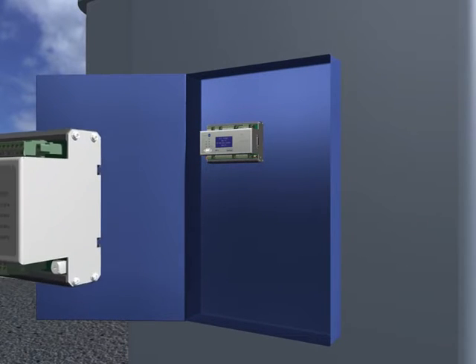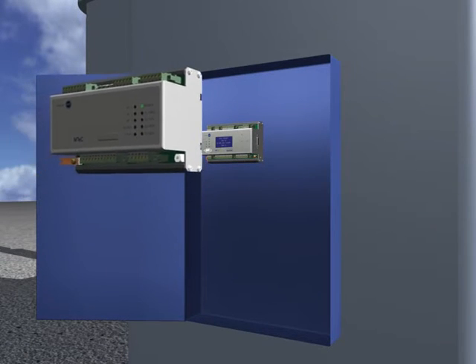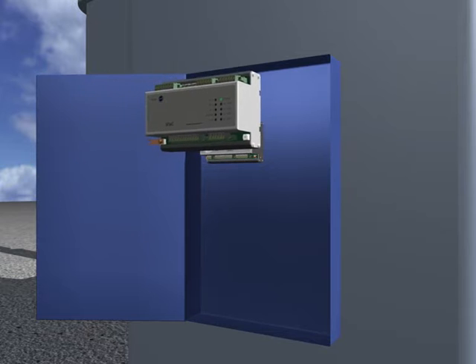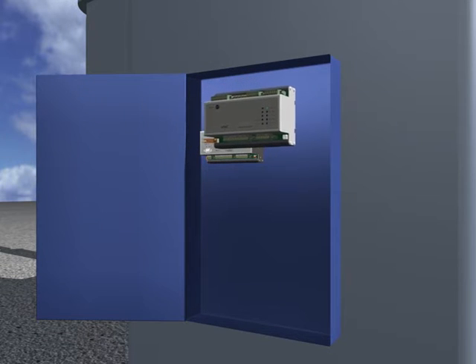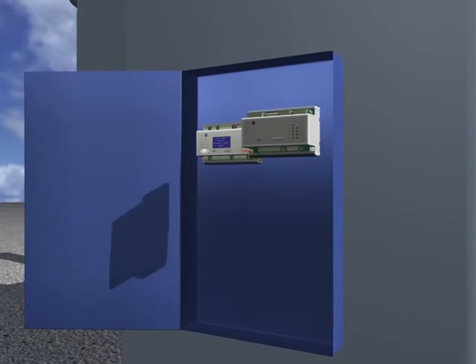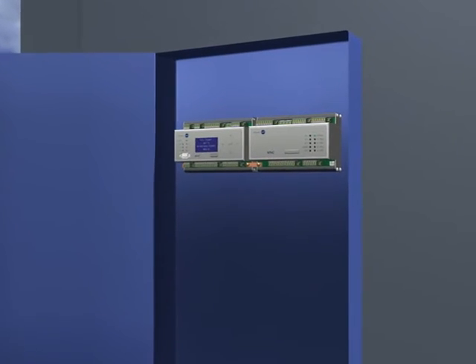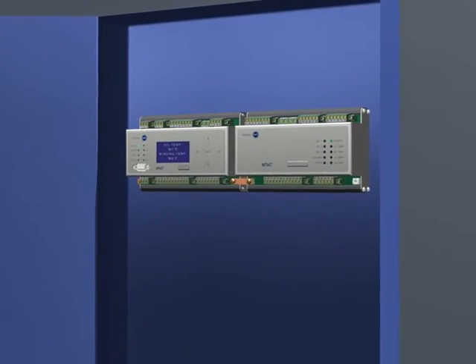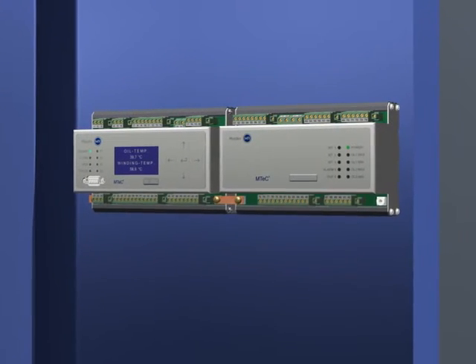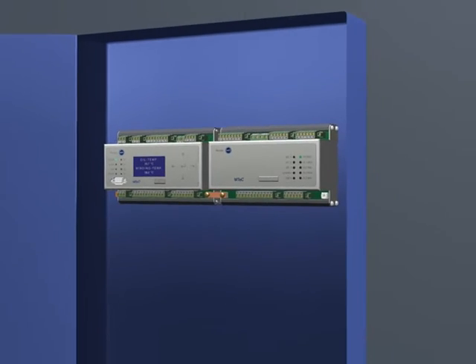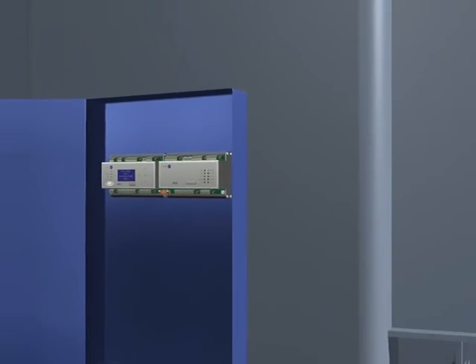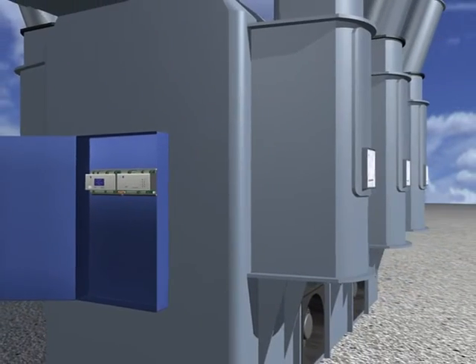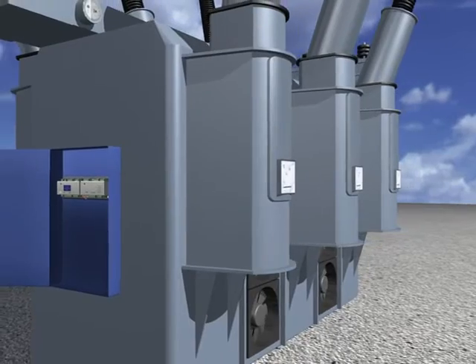Click on an extra module to expand the functionality of the MTeC system with additional circuits to monitor winding temperature and oil level. We are talking about function modularity here. It is important to measure the winding temperatures of all transformers which are equipped with cooling systems to increase loadability.